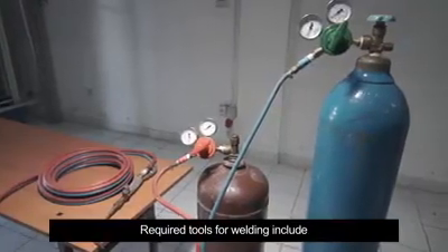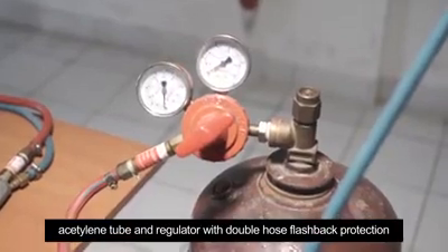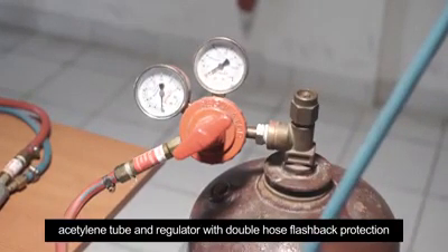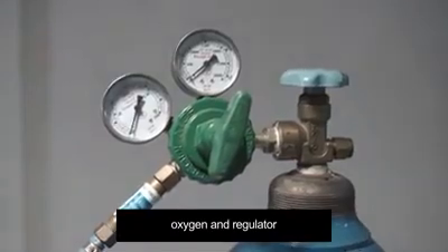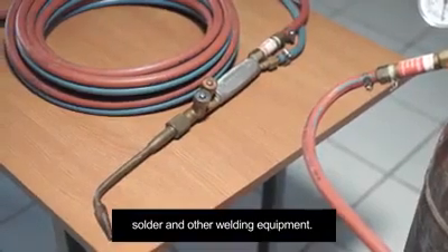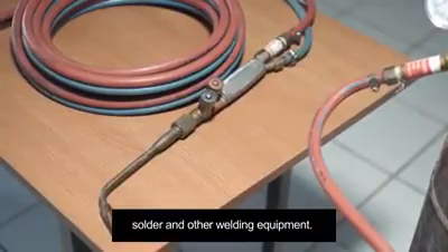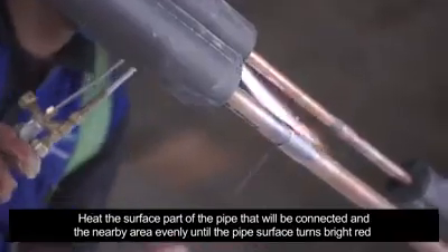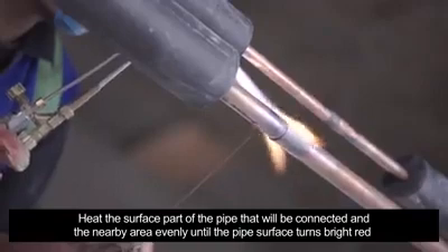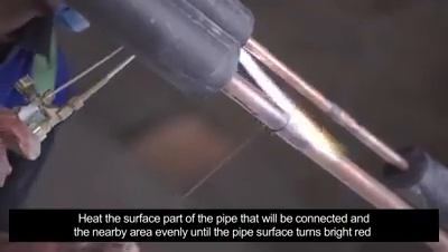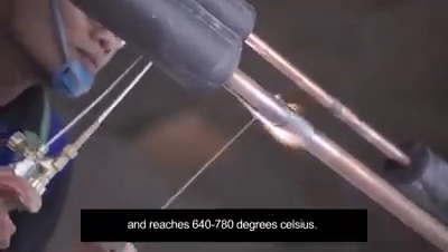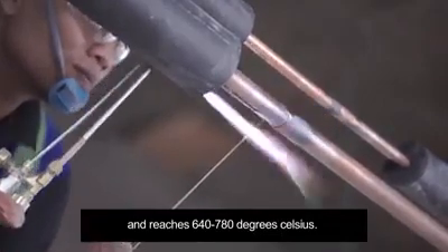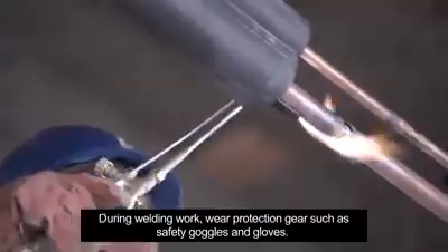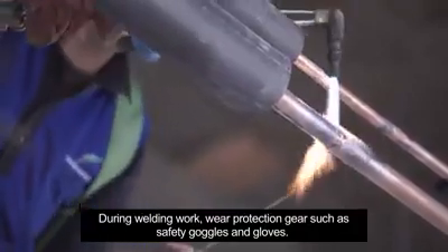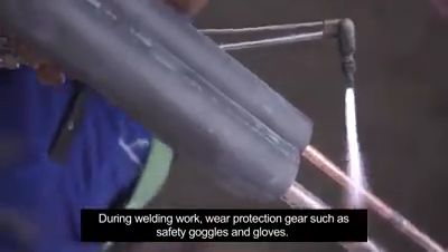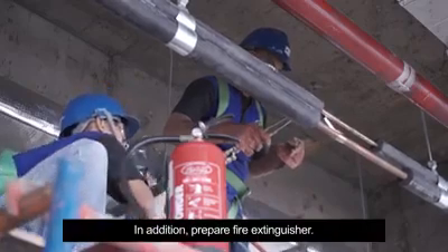Required tools for welding include acetylene tube and regulator with double-hose flashback protection, oxygen and regulator, solder and other welding equipment. Heat the surface parts of the pipe that will be connected and the nearby area evenly until the pipe surface turns bright red and reaches 640 to 780 degrees Celsius. During welding work, wear protection gear such as safety goggles and gloves. In addition, prepare fire extinguisher.